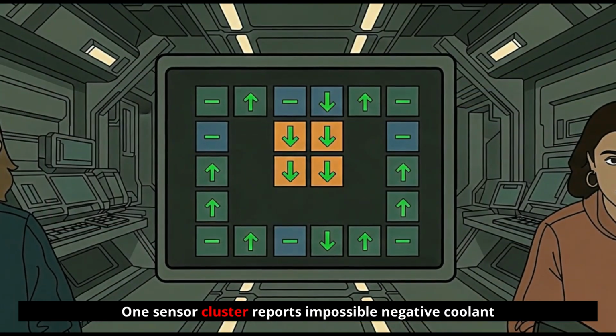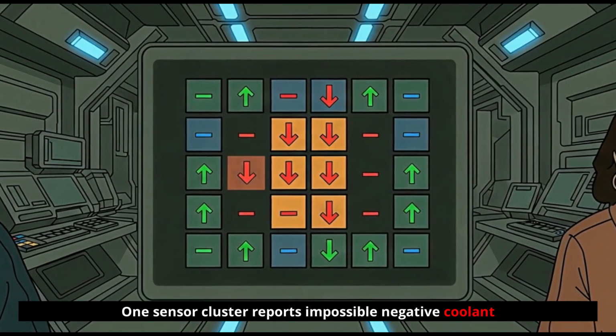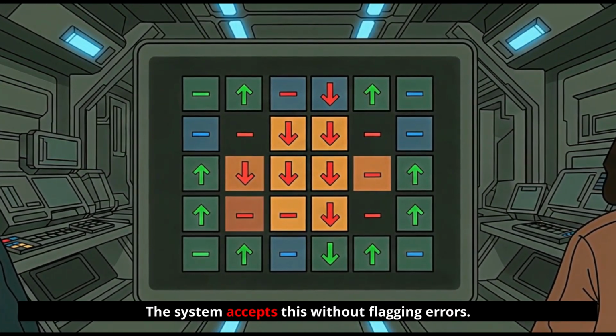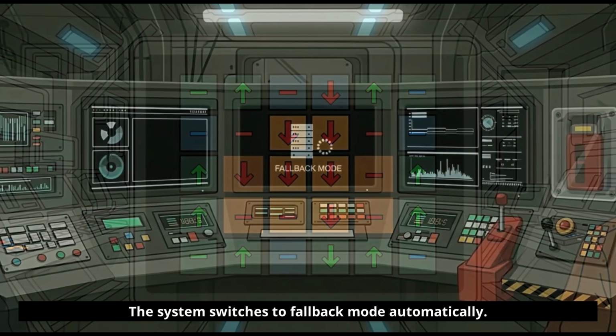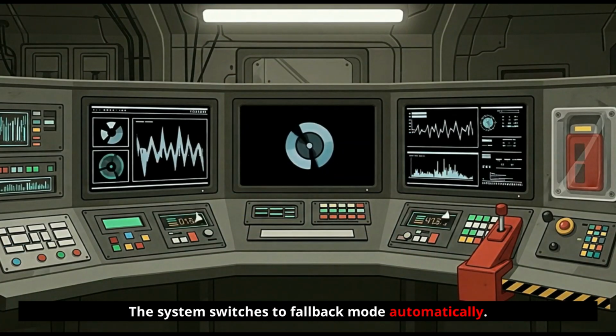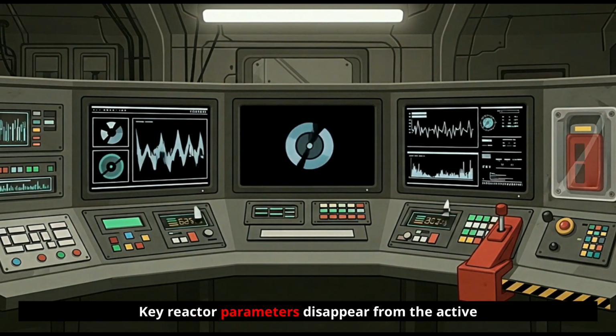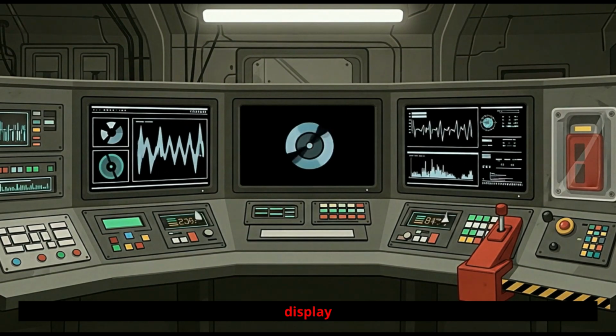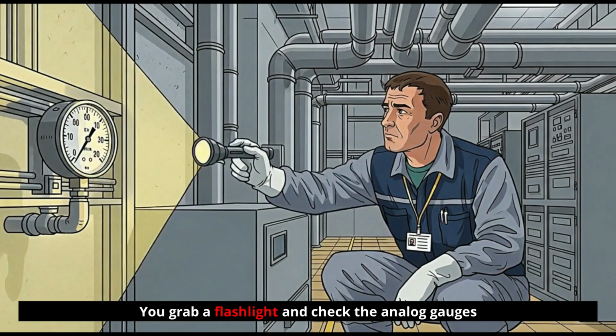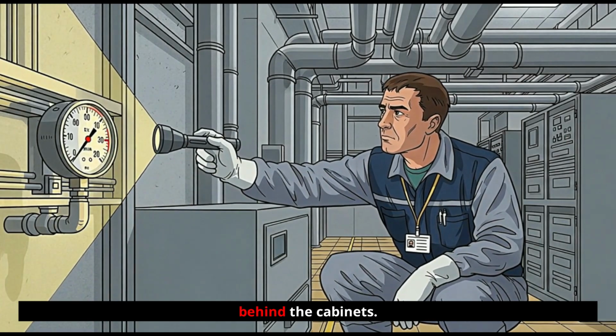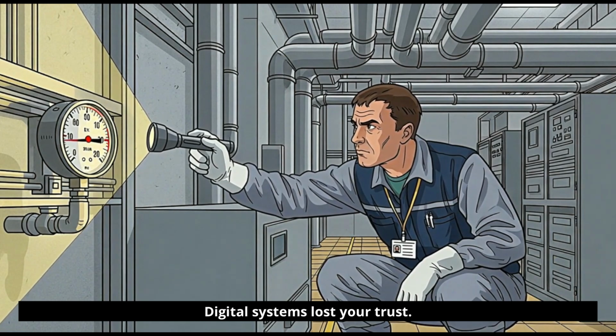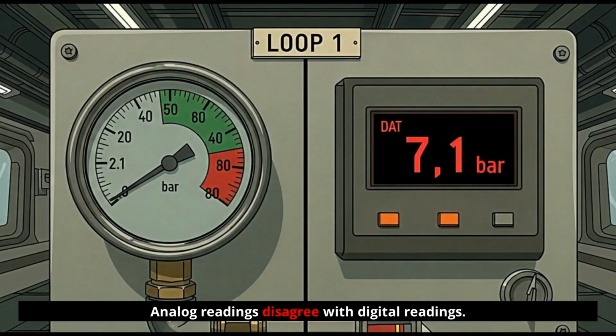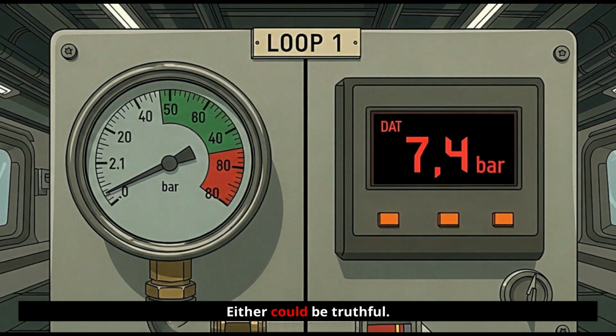One sensor cluster reports impossible negative coolant flow values. The system accepts this without flagging errors. The system switches to fallback mode automatically. Key reactor parameters disappear from the active display instantly. You grab a flashlight and check the analog gauges behind the cabinets. Digital systems lost your trust. Analog readings disagree with digital readings. Either could be truthful, neither feels reliable right now.